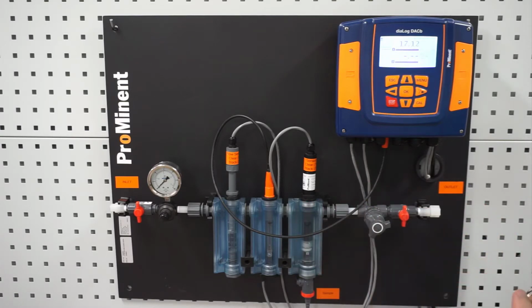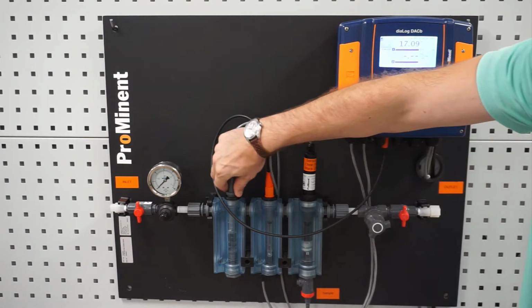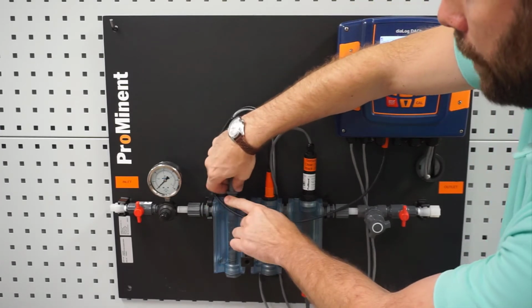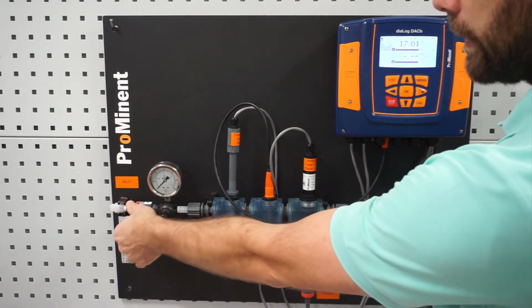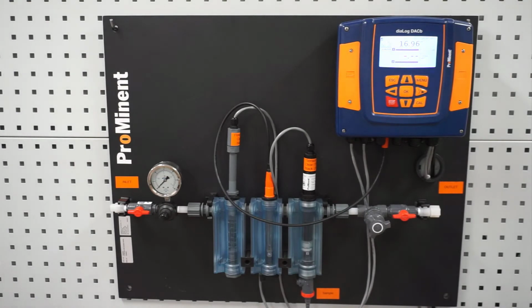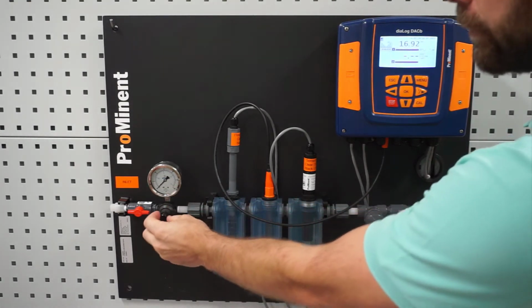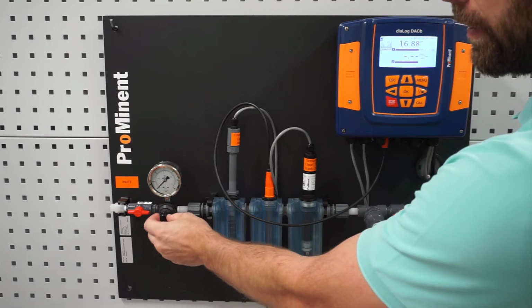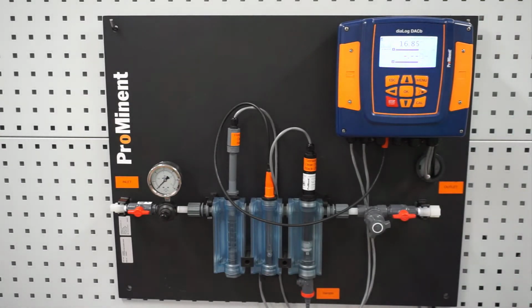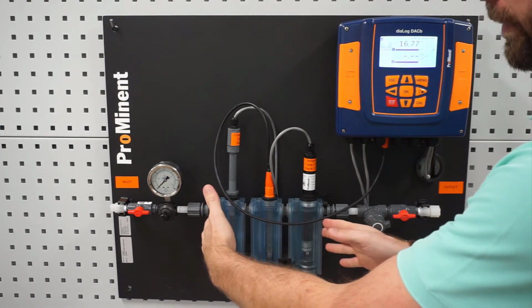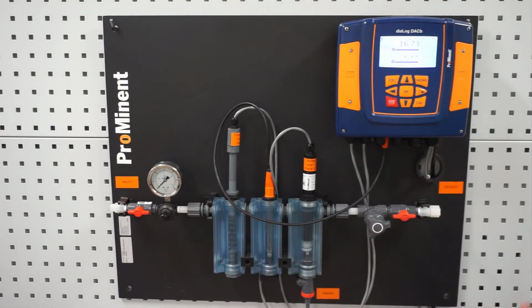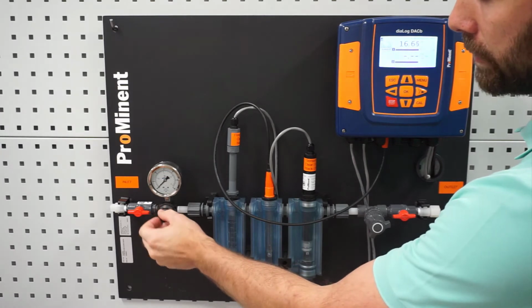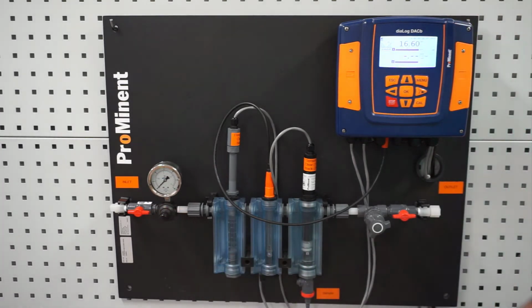Once we have our sensors installed, we need to set our pressure and flow. So what we're going to do is loosen up our flow sensor, and we're going to pull it all the way to the top and just loosely tighten it down. Once I've done that, I can introduce water into the flow cell. We want to come over to our pressure regulator. On the pressure regulator, on the adjusting knob, there is a nut there that helps lock that in place. You're going to want to loosen that. And we want to set our pressure so that it has less than 15 psi. That pressure would be what is being seen on our flow cell. So we're going to adjust that so it's not seeing any more than 15 psi. Once we have that adjusted, we can turn in our locking nut, and that will keep it in place so it doesn't work its way out.